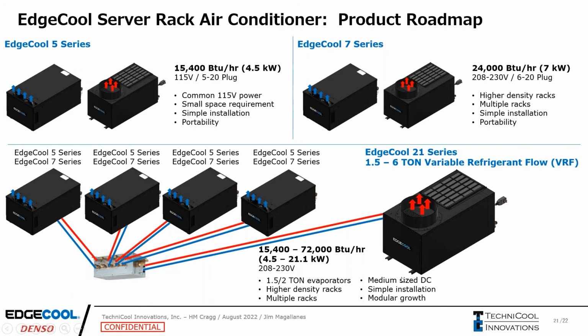What we're doing down the road here, right now with the EdgeCool 5 series, we have 4.5 kilowatts of total cooling. Next would be a higher 1-to-1 model. Again, these are 1 evaporator unit to 1 condenser unit. We're looking to come out with a 2-ton unit, 24,000 BTUs, 7 kilowatts of cooling, operating at 230 volts, 20 amp circuit. This would be for higher density racks, multiple racks. Again, you still have the simple installation and portability that comes along with it.